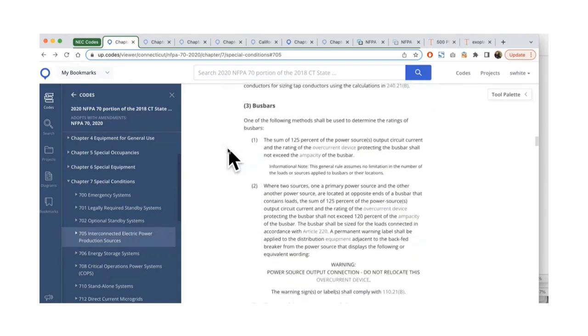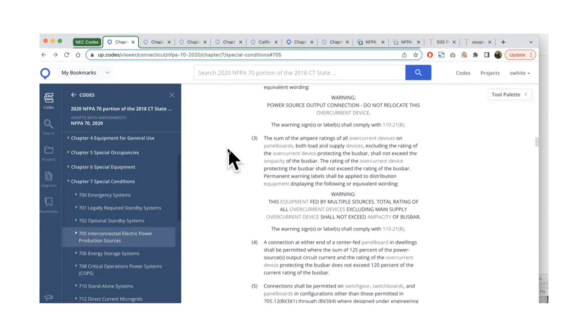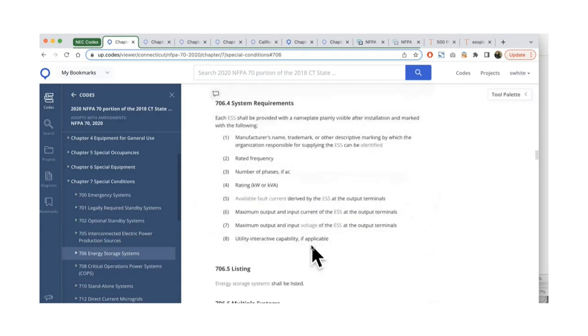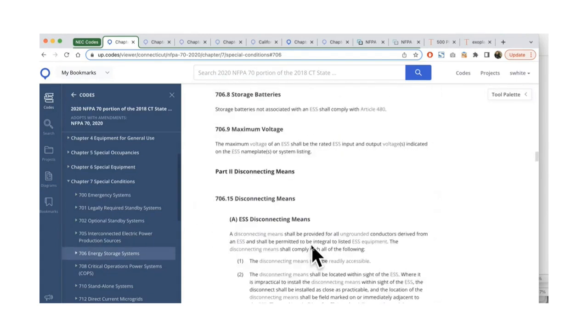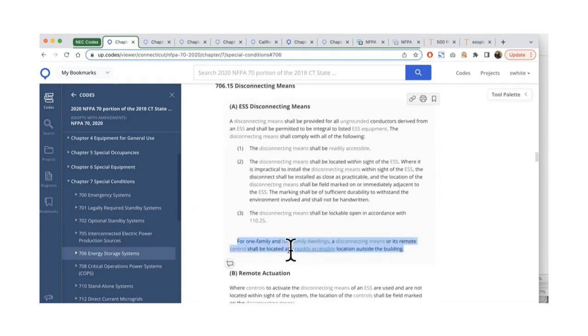It's the tricky part is when you have backup. And then with backup, you need to have the energy storage system disconnect. Like here, and it says 1 and 2 family dwellings, disconnecting means or its remote shall be located readily accessible outside the building. Does that clarify that?